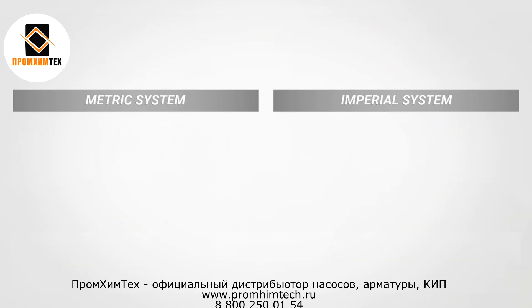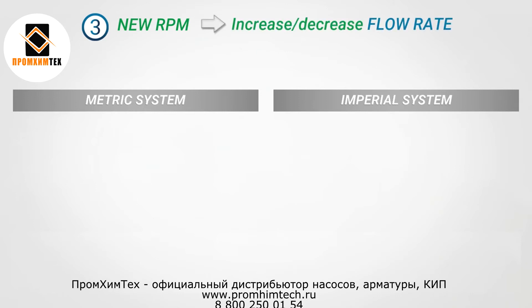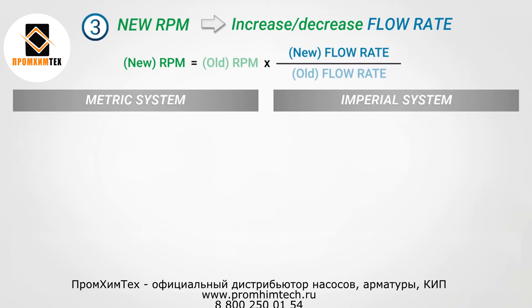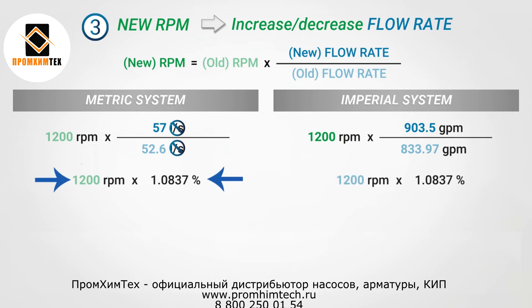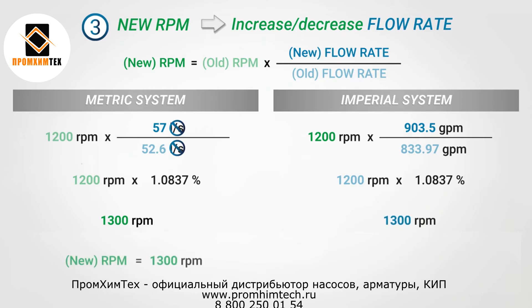The next value we are going to calculate is the RPM of the pump: what RPM do we need if we want to increase or decrease the flow rate? The new RPM equals the old RPM value multiplied by the division of the new flow rate by the original flow rate. Following this calculation, you cancel out the liters per second and find a ratio that, multiplied by the original RPM, results in 1300 RPM — the rotation speed the impeller must reach to sustain the new flow rate.